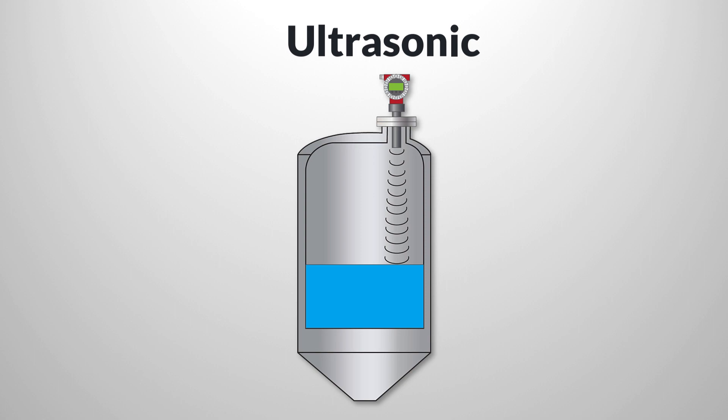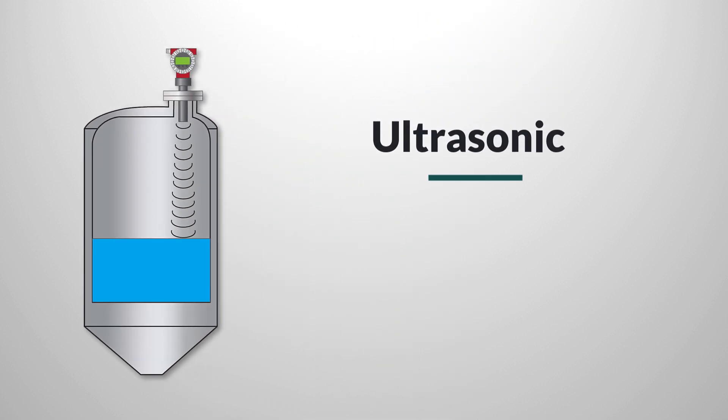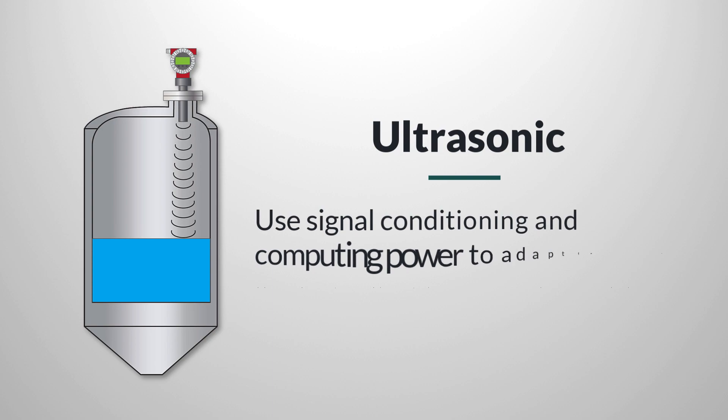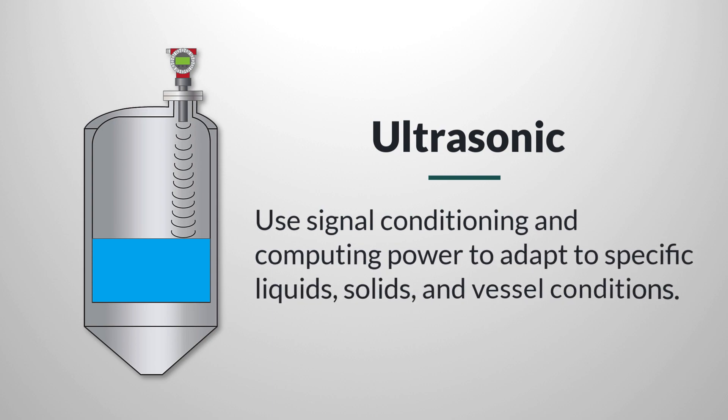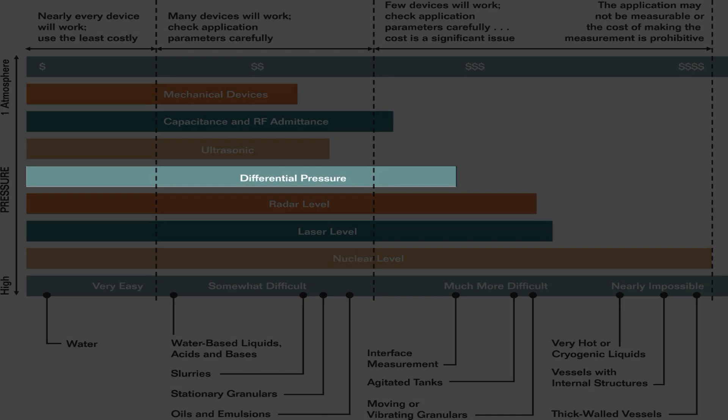Ultrasonic gauges are also quite versatile and offer good value. Ultrasonic gauges calculate level based on the time required for an ultrasonic signal to be reflected from the liquid surface. They, and the other time-of-flight gauges coming later, use signal conditioning and computing power to adapt to specific liquids, solids, and vessel conditions. They are seeing increasing applications as the cost of signal conditioning and computing have come down.